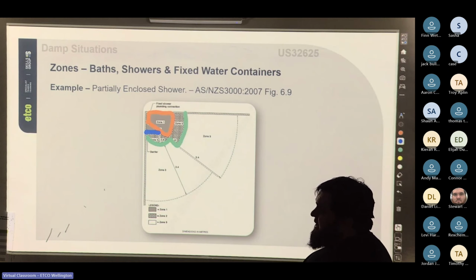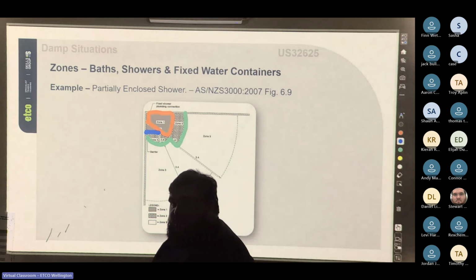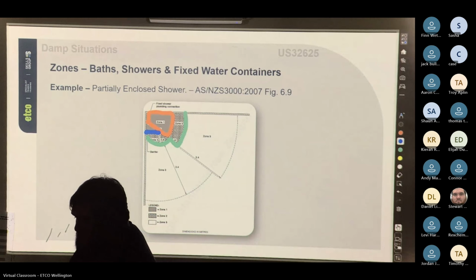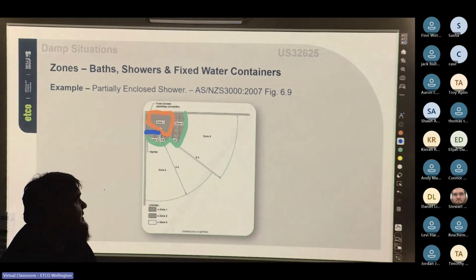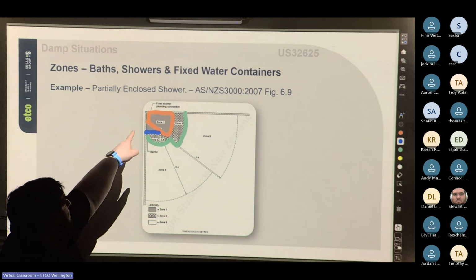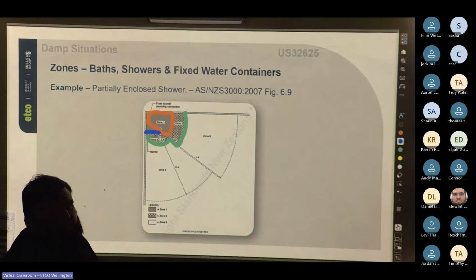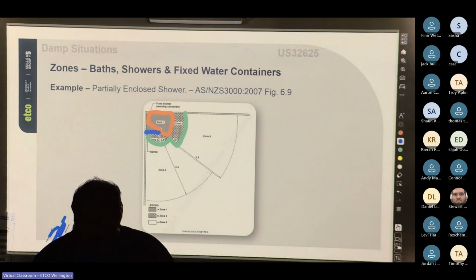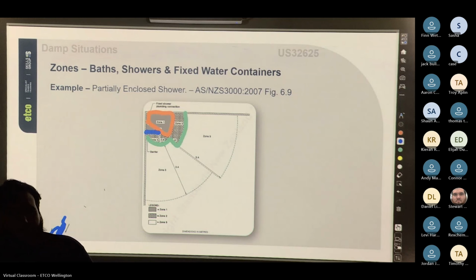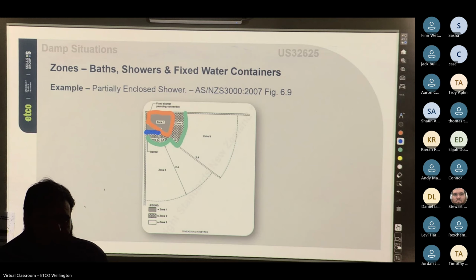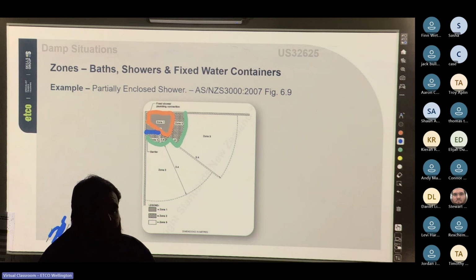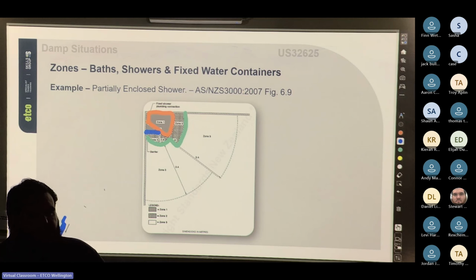So this is what happens when we have a partially enclosed shower. Once we start moving into a movable shower head, we still reference it from the fixed plumbing connection. So if we have a movable shower head, as far as 3000 is concerned, nothing really changes, because it's from the fixed plumbing connection point. I mean, realistically, it is a judgment call. If I see that there's a shower with a movable head, I'm going to maybe go a bit further than my zones.